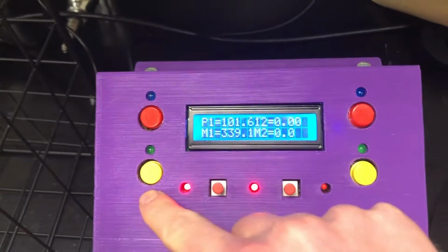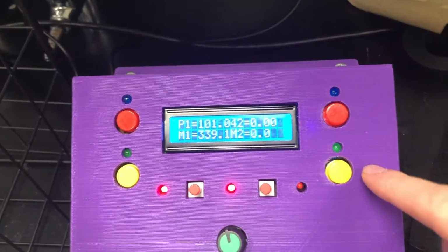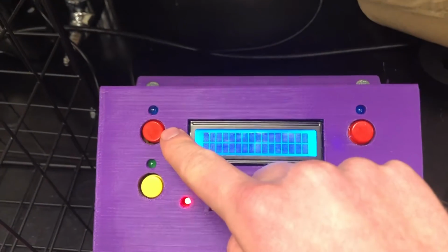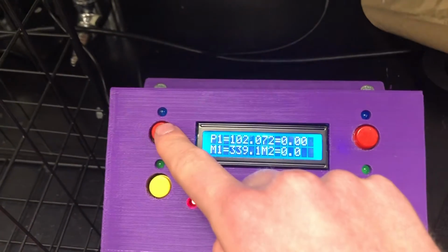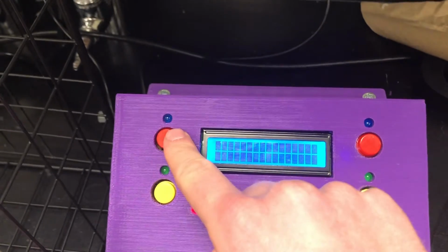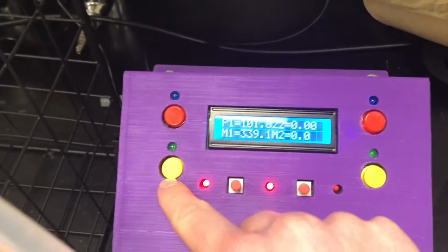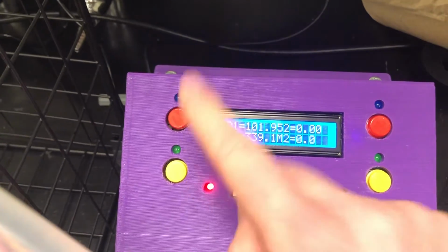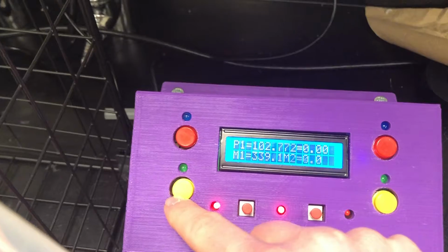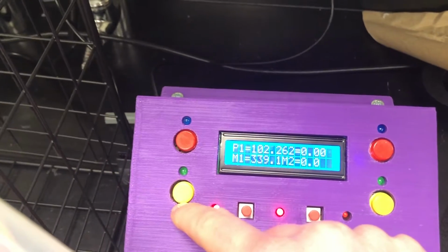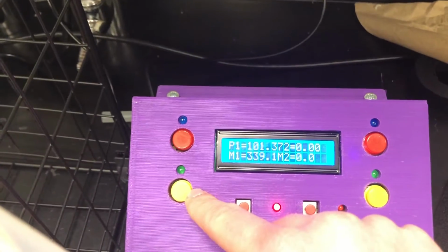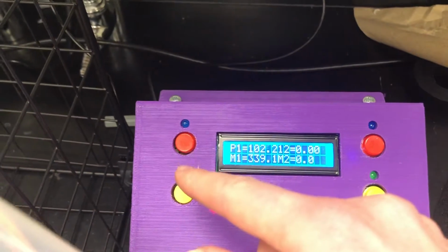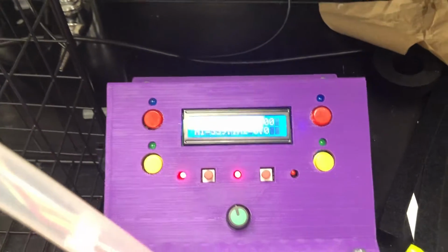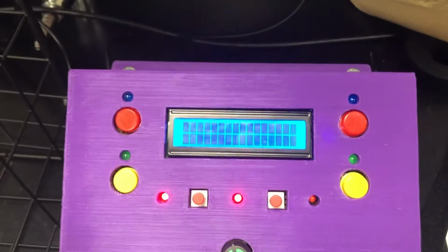These buttons all across here are our calibration values. So the button right here takes the high voltage associated with the pressure value, in this case 200, and this one takes the low value, which in this case is 50 millimeters of mercury. After you press the second button, it determines the slope value, and the program continuously determines the slope value, and that's how you get the calibration curve for the system.